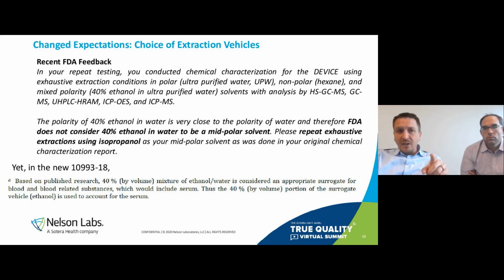And then the FDA said the polarity of 40% ethanol and water is very close to the polarity of water. And therefore, the FDA does not consider 40% ethanol to be a mid-polar solvent. Please repeat exhaustive extraction using isopropanol. So this is a case where a really rational scientific approach was applied to the testing and the extraction conditions, but the FDA was really digging in their heels on wanting to see what they view as 3 standard solvents: water, IPA, and hexane.